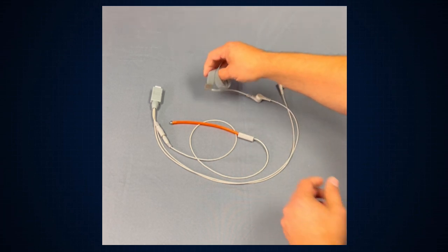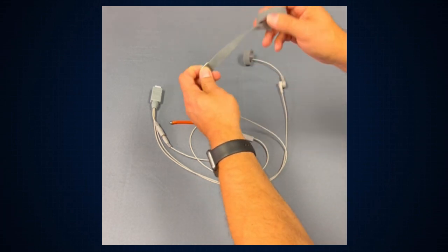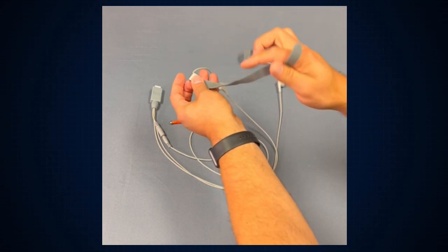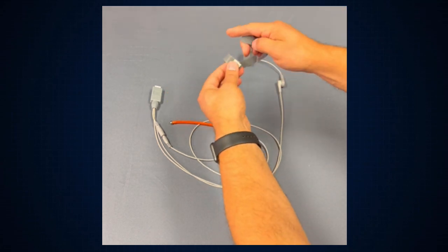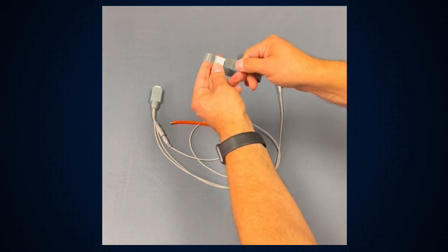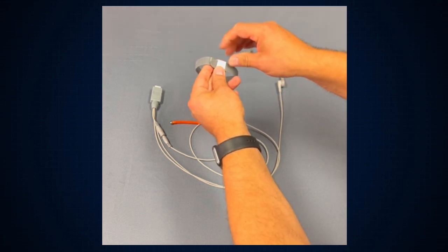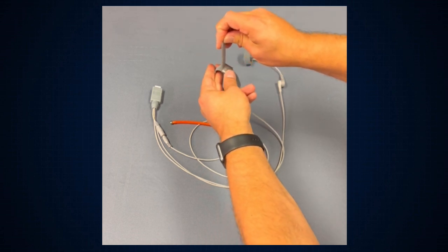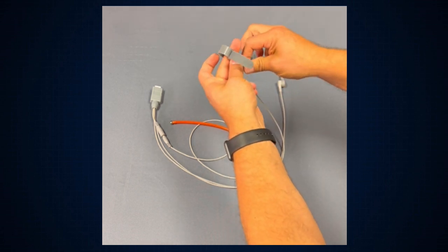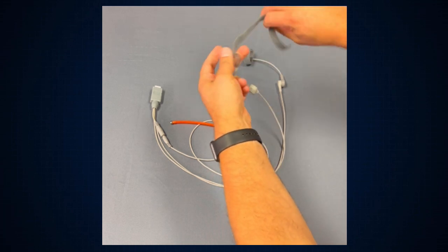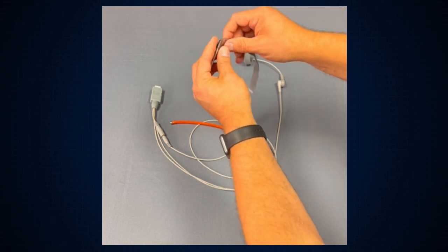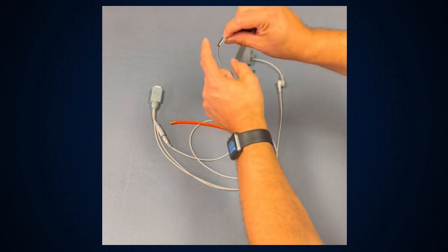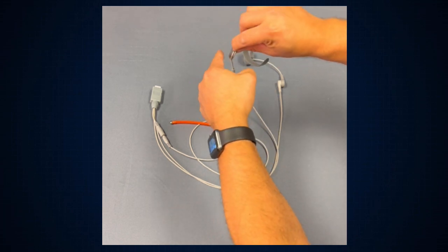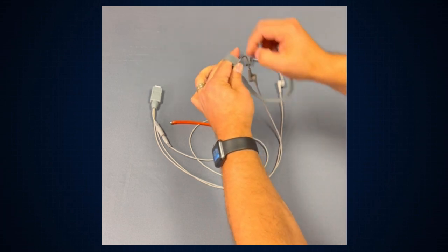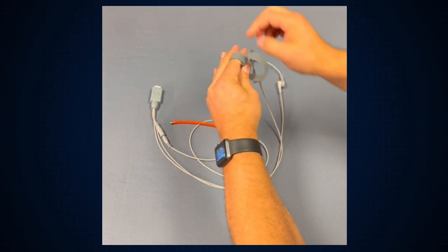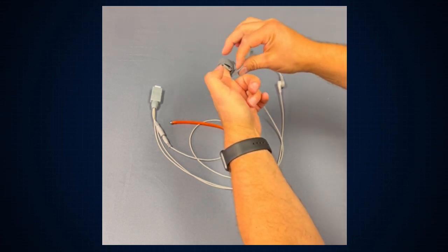To physically attach the ECG limb plate to the body, you certainly can go through the buckle. That will allow you to get more of a cinched connection to the patient. Again, just put that right through the buckle, such as so, and then pull the Velcro back towards you. That will allow it to stay on better. Or you can simply just apply the metal contact right against the patient's skin. There is no need to clip the fur. Just again, apply it right to the limb, take the strap, wrap it around, again ensuring that the metal contact plate is right against the fur.